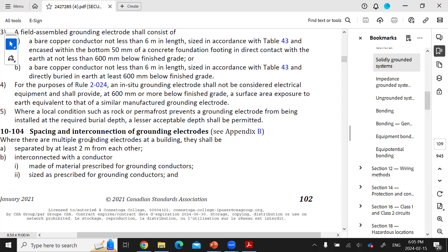It says that where multiple grounding electrodes are used, they should be separated by at least two meters from each other. And they should, of course, be bonded together with a conductor.